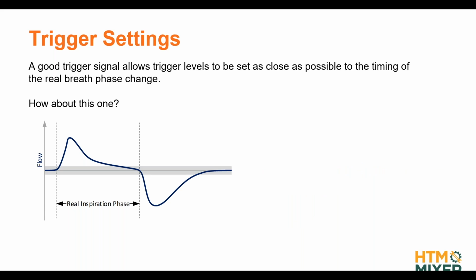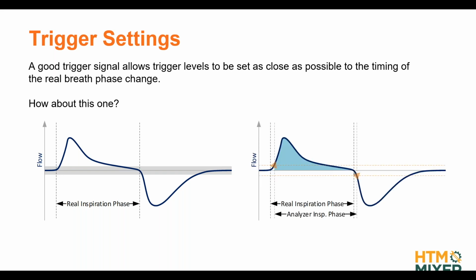Better? Yeah, definitely going to be better, right? Because now here we have a positive flow in the inspiration phase and a negative flow in the exhalation phase. We have quite steep slopes here at both breath phase transitions, right? By the way, this is very typical for a ventilation testing application, right? You have positive flow and negative flow through your analyzer. Yeah, so let's have a look. Here we can set our triggers on a rising edge here, right above our gray area for the start trigger. And then because here it goes negative, we can go on a negative value on a falling edge. And our analyzer detected inspiration phase is very, very close to our reality, right?